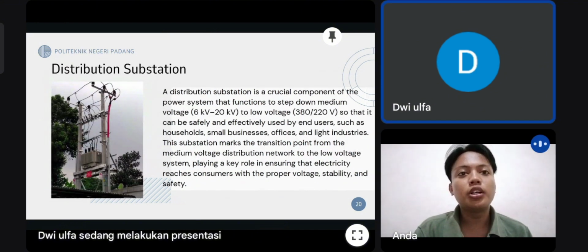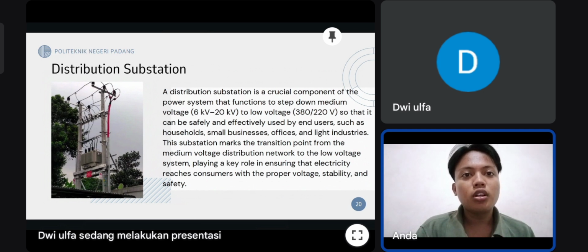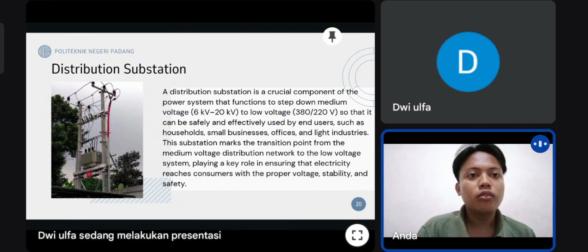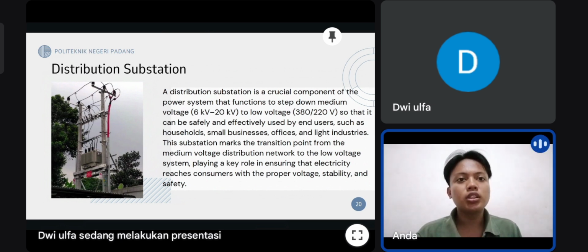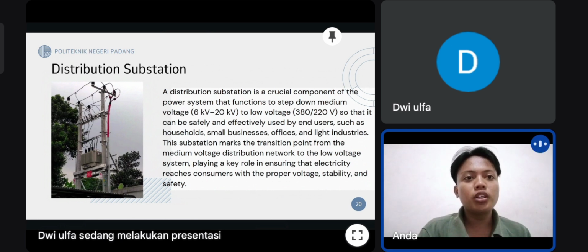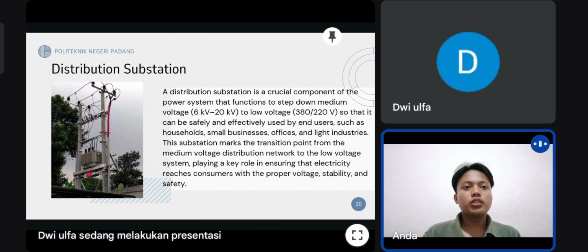Distribution substation. A distribution substation is a crucial component of the power system that functions to step down medium voltage, 6 kV to 20 kV, to low voltage, 380 or 220 volts, so that it can be safely and efficiently used by users such as households, small businesses, offices, and light industry. This substation makes the transition from the medium voltage distribution network to the low voltage system, playing a key role in ensuring that electricity reaches consumers with the proper voltage, stability, and safety.